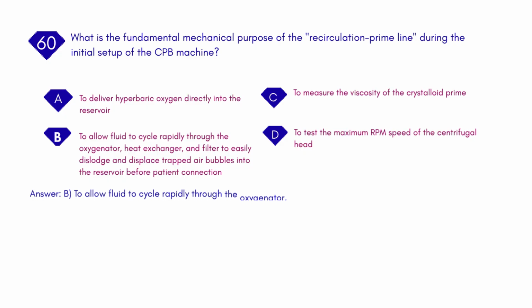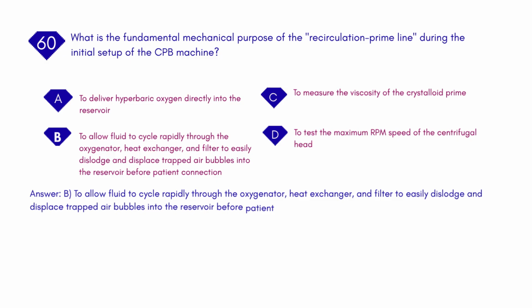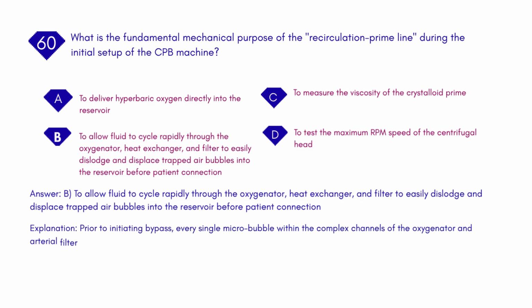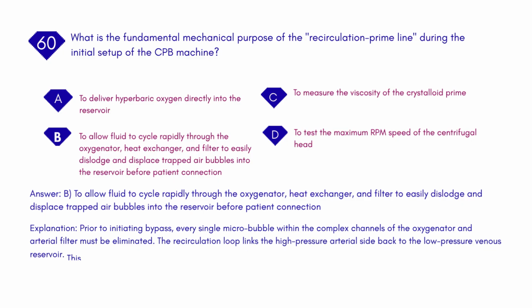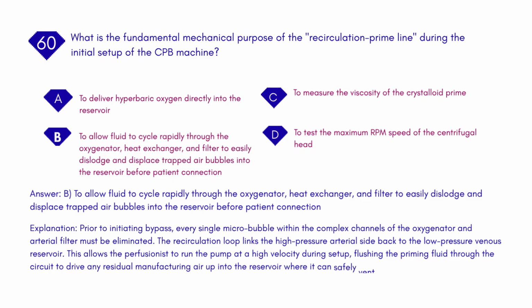Answer: B. To allow fluid to cycle rapidly through the oxygenator, heat exchanger, and filter to easily dislodge and displace trapped air bubbles into the reservoir before patient connection. Explanation: Prior to initiating bypass, every single microbubble within the complex channels of the oxygenator and arterial filter must be eliminated. The recirculation loop links the high-pressure arterial side back to the low-pressure venous reservoir. This allows the perfusionist to run the pump at a high velocity during setup, flushing the priming fluid through the circuit to drive any residual manufacturing air up into the reservoir where it can safely vent to the atmosphere.